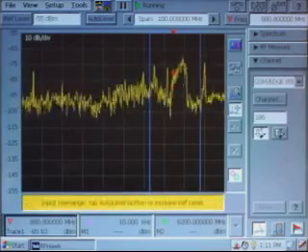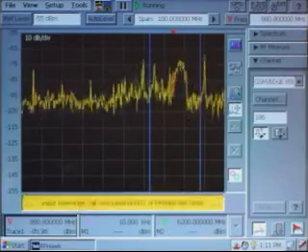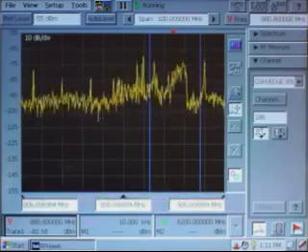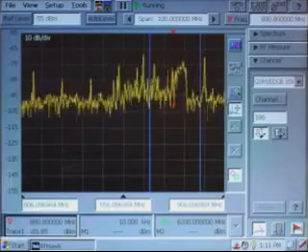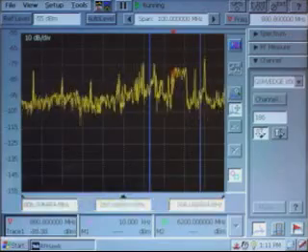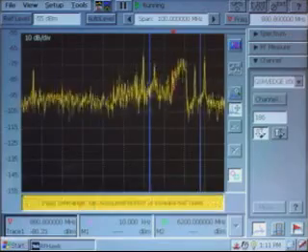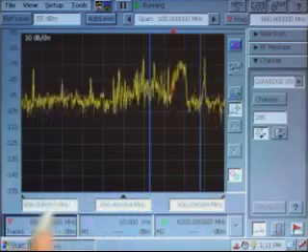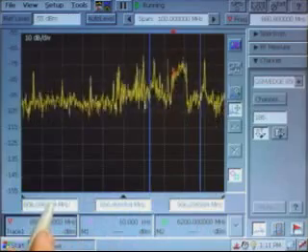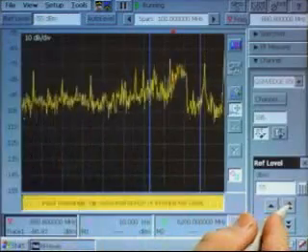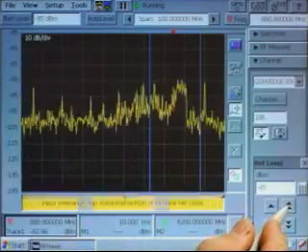Once at that level though, you may sometimes find that a strong out-of-band signal has shown up, which requires more adjustment. That's indicated by this yellow banner. In that case, by pressing the reference level box, you can manually set the reference level to whatever you want.